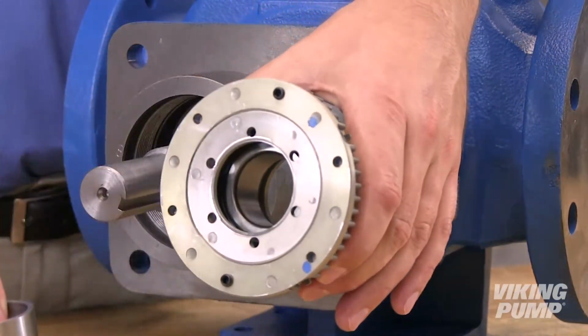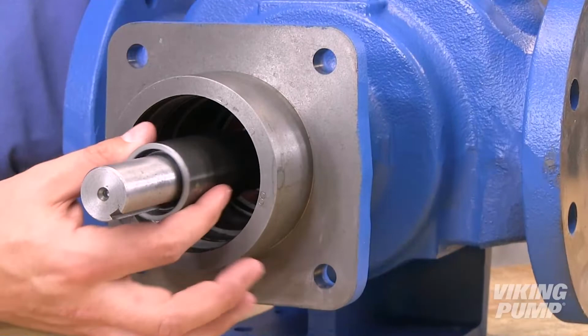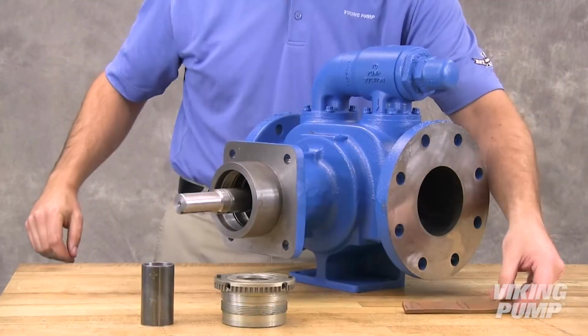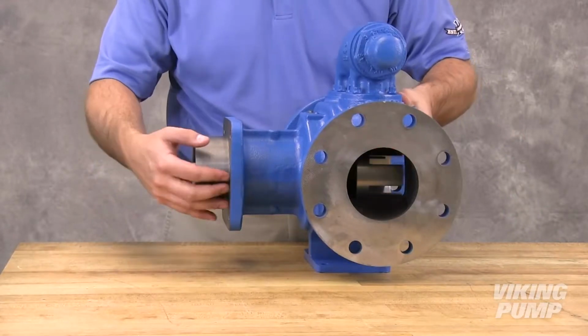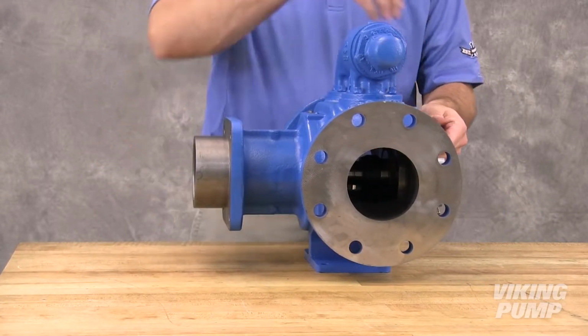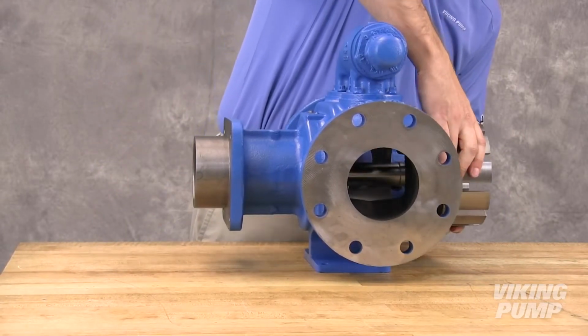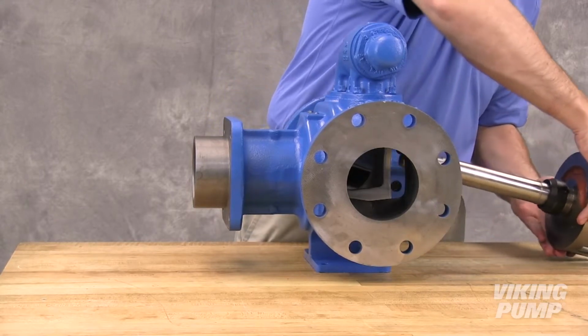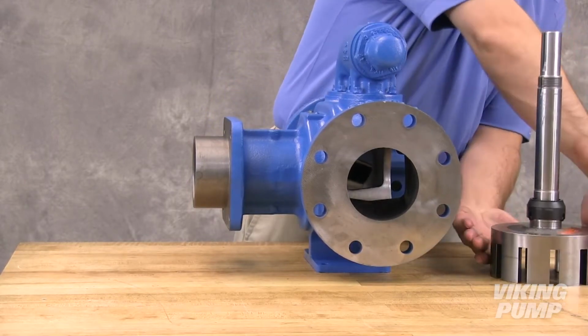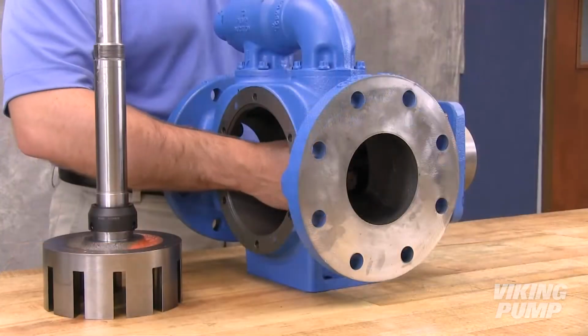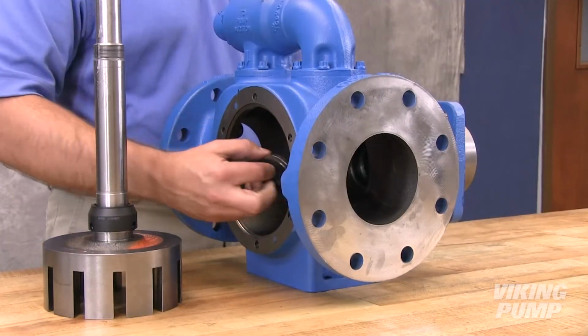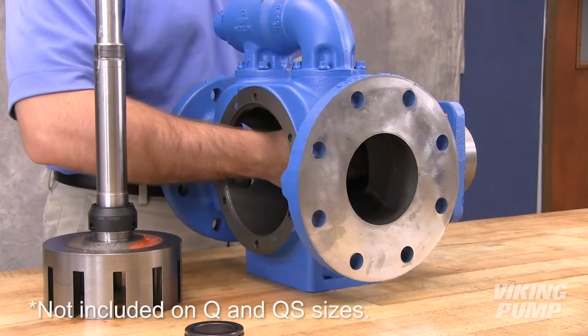Remove the bearing spacer collar. Remove the bearing spacer from the shaft. Remove the brass bar. The rotor shaft assembly can now be removed from the pump. A soft-headed hammer may be needed to tap on the end of the shaft to aid with removal. The rotary member of the seal will come out with the rotor shaft. Remove the stationary seat from the casing bore. Remove the bearing spacer collar.